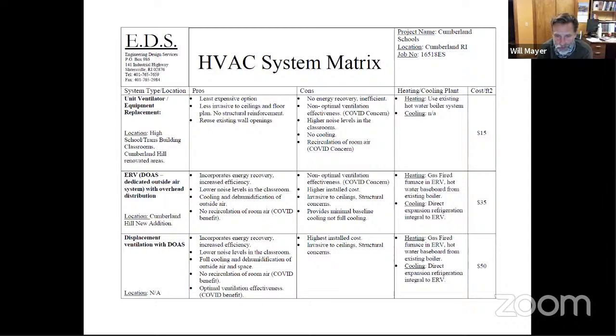As I was saying, these unit ventilators can certainly handle a MERV 13 filter. There's really no change required. It's got a 2-inch filter rack, and the 2-inch filter rack will accept a MERV 13 filter. And we would just look at the static pressure loss through that filter to make sure that we weren't losing too much airflow.